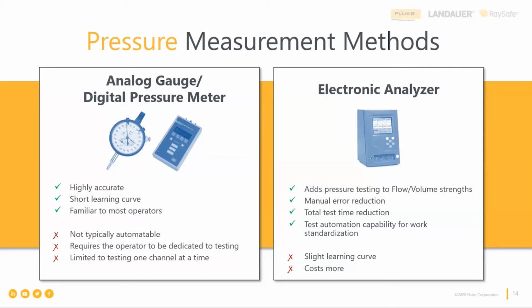Which is why most of the modern infusion pumps have safety systems that trigger an alarm sound when an internal pressure in the pump reaches a certain level, when an occlusion or a blockage happens. So our goal is to check pressure in infusion pumps, as well as record the pressure level at which the occlusion alarm is activated to make sure that everything is working properly. So how can we do that? There are two ways to do that. We can either use an analog gauge or a digital pressure meter as one sort of setup, or we can use the same digital analyzer that we talked about in the volume flow rate testing a slide before.